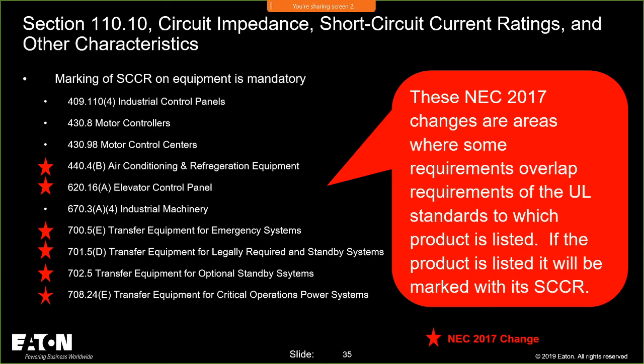But in any case, all of the equipment that you see here, all of the transfer switches in 700, 701, 702, 708, are going to have special requirements. In the 17 cycle, we have to mark the short circuit current rating of that equipment because it is dependent upon how it's installed, what is supplying it. They call it a withstand close-on rating, but in any case, the short circuit current rating or the withstand close-on rating is going to be dependent upon the overcurrent device upstream from it. I think there's a similar issue with 700 and transfer switches that we'll have with panel boards and switchboards. But in any case, we'll cover that one a little bit more.